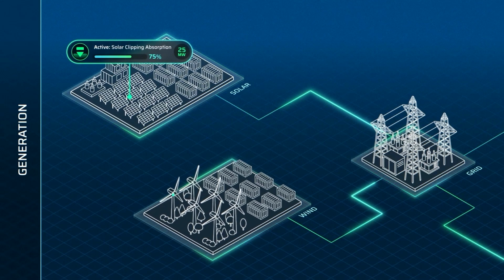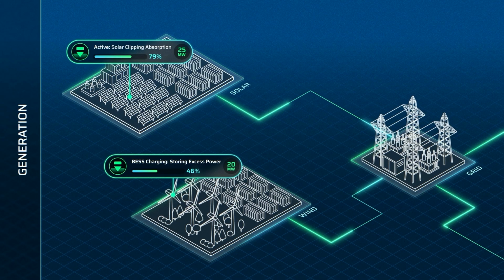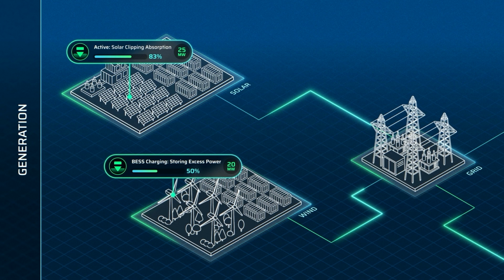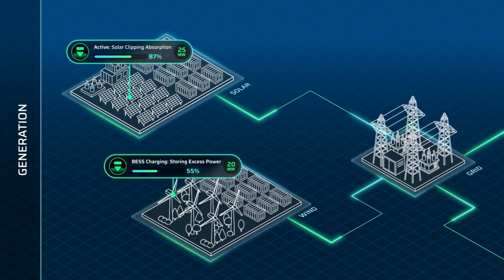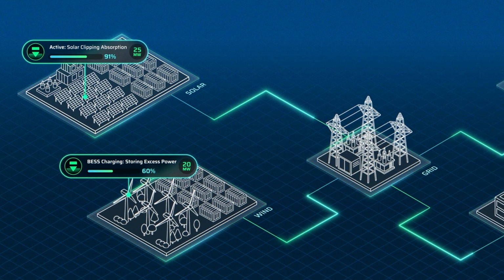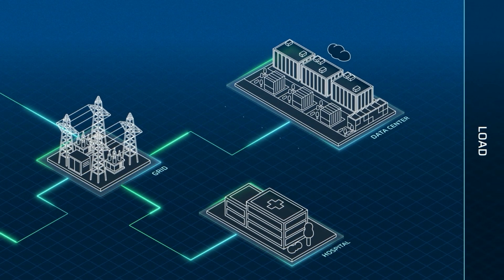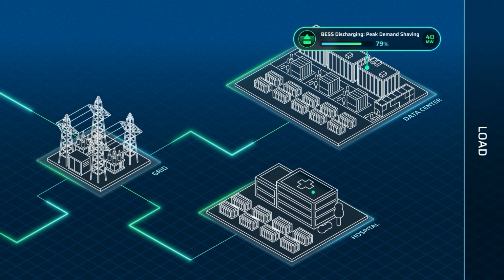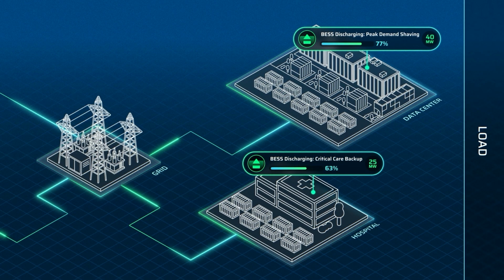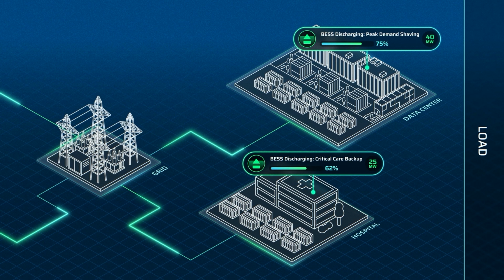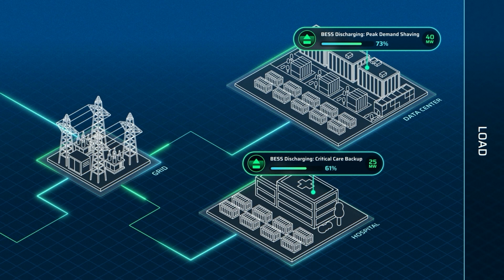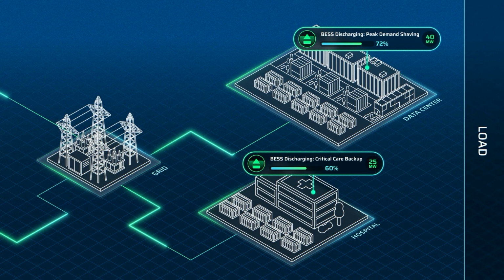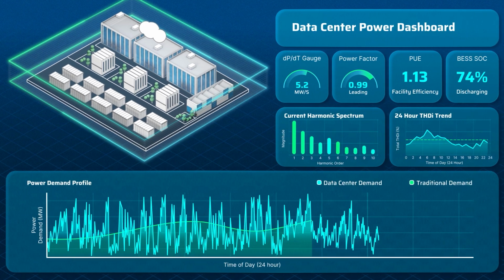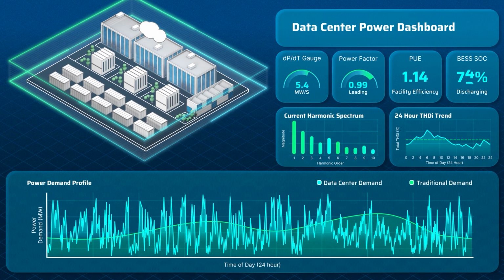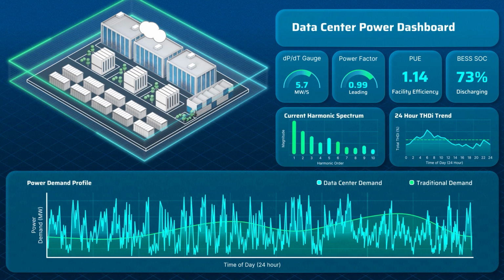Co-location originated on the generation side of the meter, where pairing batteries with intermittent generation sources like wind and solar has become a well-utilized solution to firm up output. Today, co-location is also an essential architecture on the load side of the meter, solving a new set of critical challenges. It is being deployed where frequency and voltage volatility is highest and where pristine power quality is a non-negotiable requirement. Nowhere is this more evident than the hyperscale data center. Operating at hundreds of megawatts with rapid power variability, they challenge the foundations of conventional power system design.